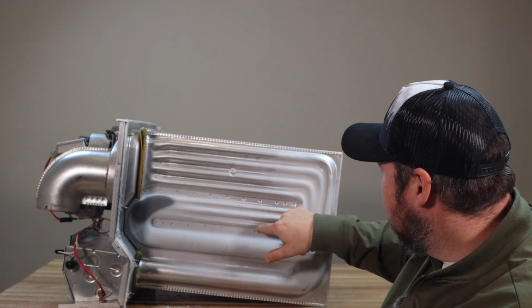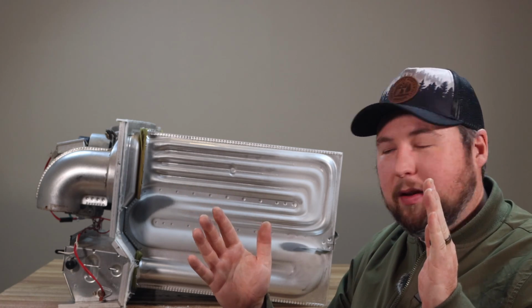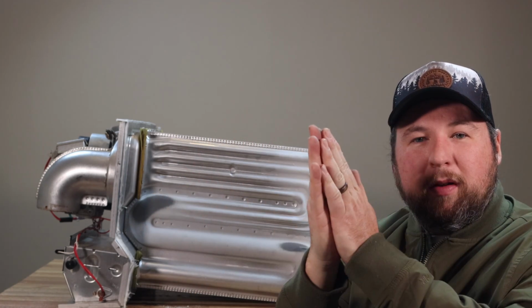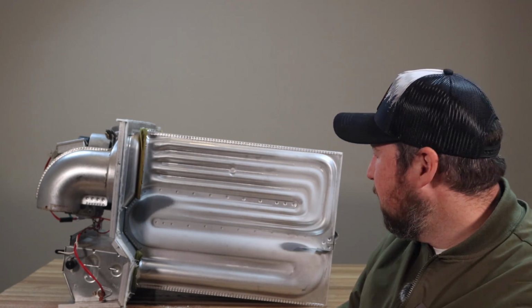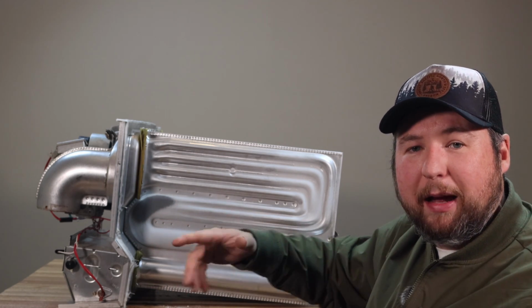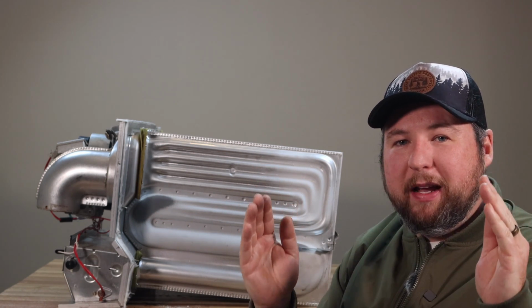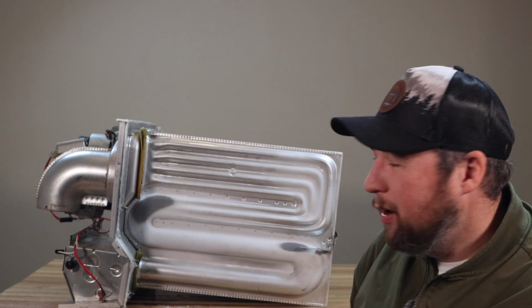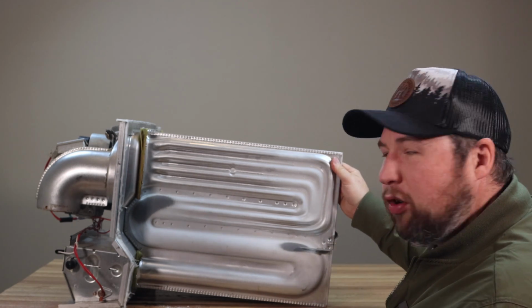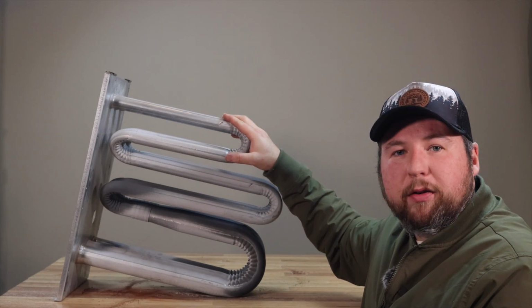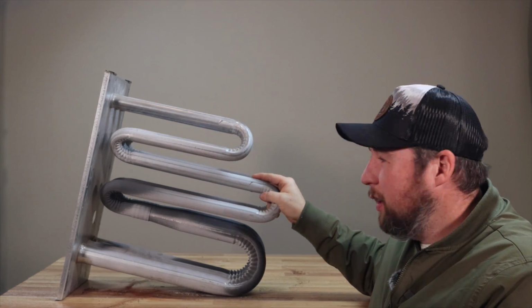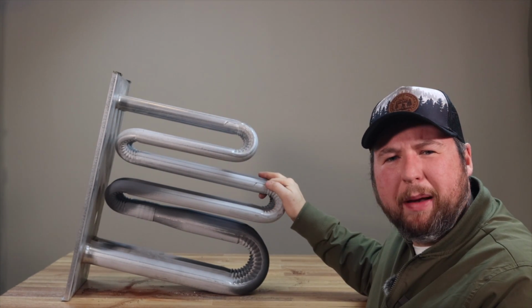Now basically what this is, two pieces that are stamped, you know, one side of the tube, squish it together. Kind of like a clamshell, the only difference is it actually has this space. The clamshells were just two big open spaces, and you put the burners right in. But let's show you what a tubular looks like. So this right here is a tubular heat exchanger off of an 80% furnace. I believe it was off of a package unit.